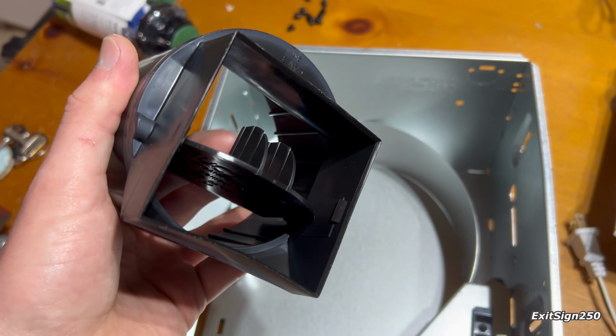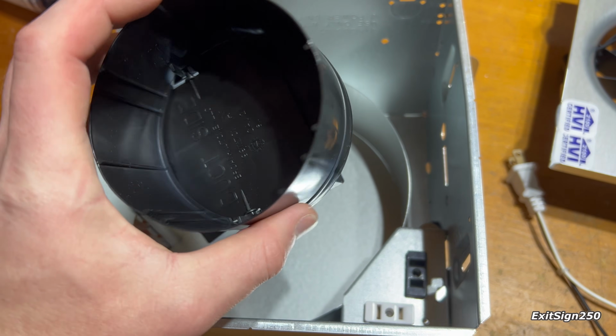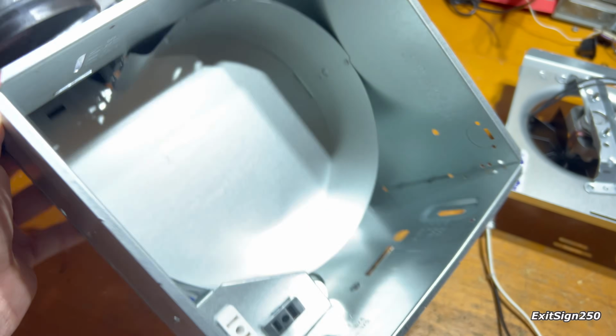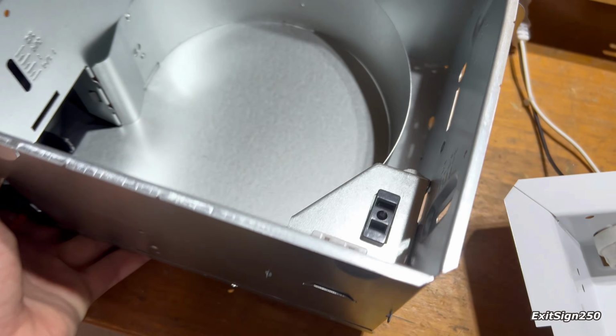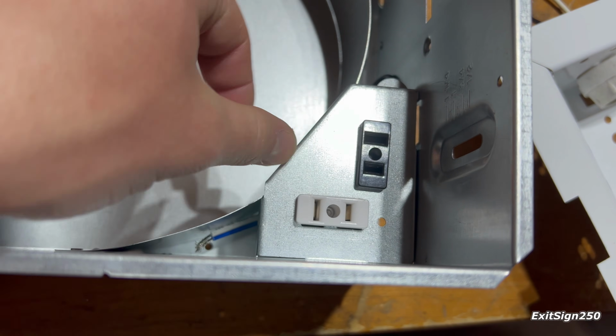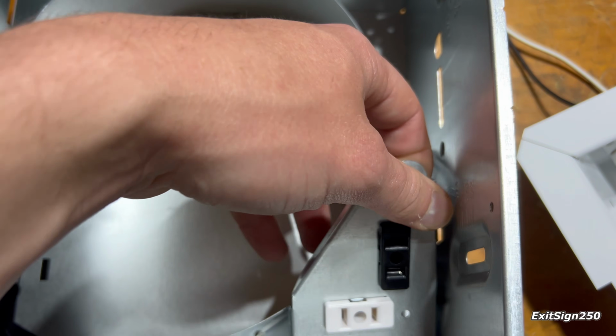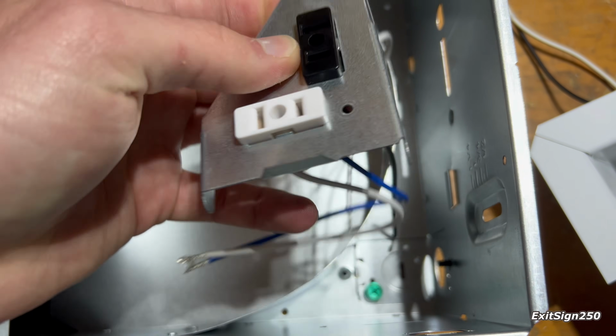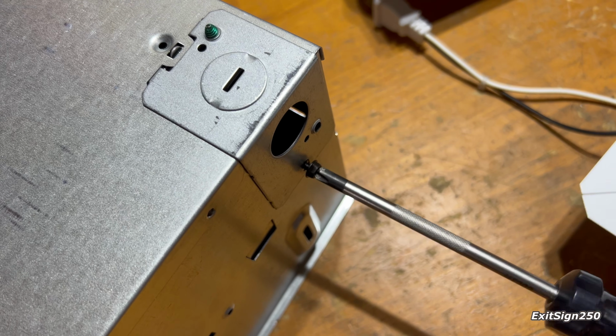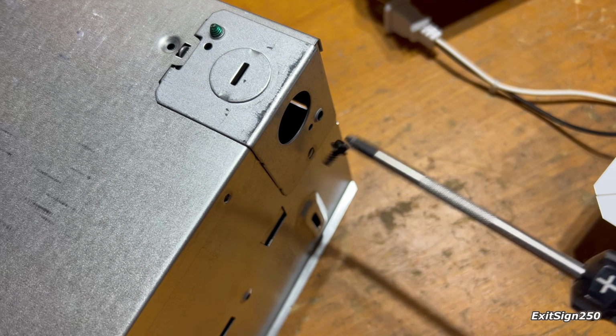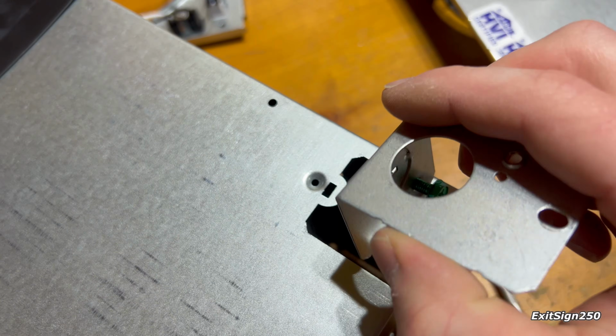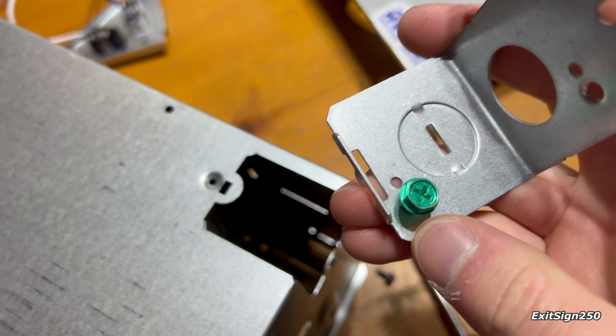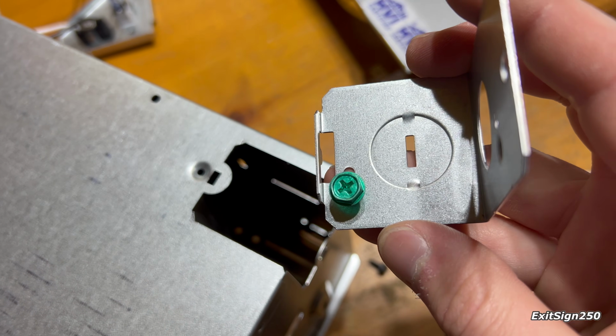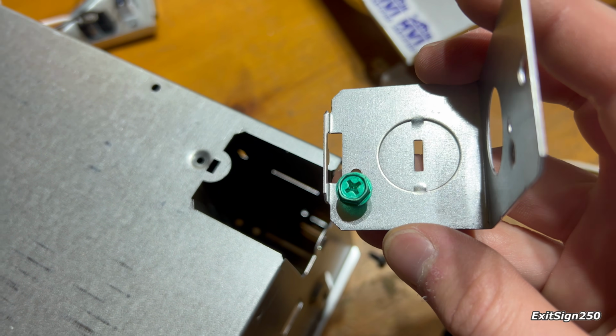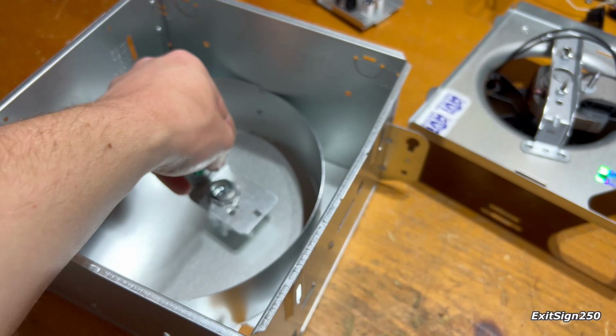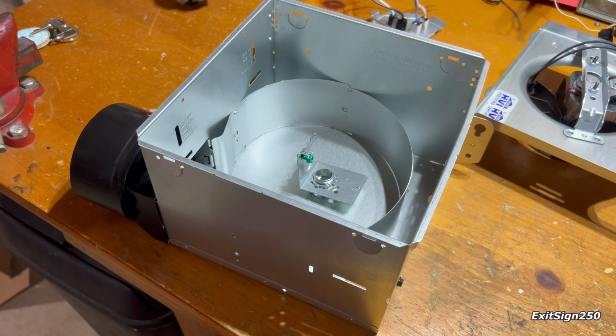Now we need to assemble the duct outlet - that's in, it pretty much just snaps into place. I need to remove this little junction box, and it pretty much just pops open like that. Next, I'll be removing this little L-shaped plate because we need to install a cable clamp, and this is the ground screw which our ground wire will connect to. The cable clamp is in place, so this new exhaust fan is ready to be installed.